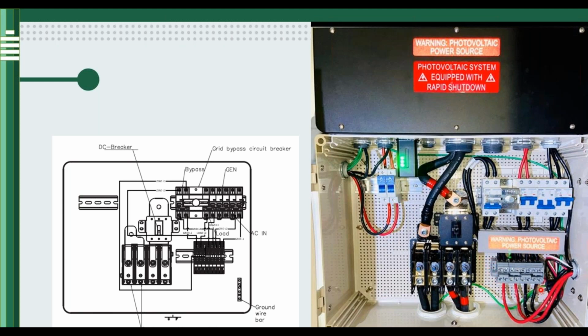These cable connections already come with the MV distribution panel to make that bypass feature. This is where you would connect all your AC input and output, AC input coming in, and then going into the ports of the MV8K and 10K, and then load coming out, going into the power blocks here, right? It can tolerate up to 2 battery connections, as we see here, also using compression terminals. And it does have a little DIN rail, so you can put your fuse breakers to disconnect PV as well.